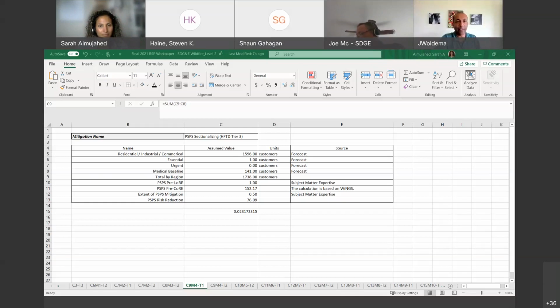So it depends. We have system protection settings at the substation, and those settings would change to accommodate the additional switch, because the sectionalizing devices come with devices we set for protection. So there are settings adjustments that go with the new sectionalizing device. Everything upstream, as well as the substation, is adjusted to accommodate it, but not drastically. The new sectionalizing device is also adjusted to fit the characteristics of the circuit and its location.